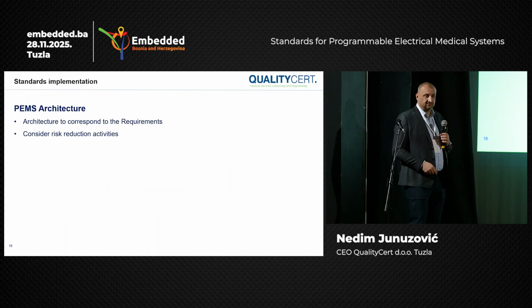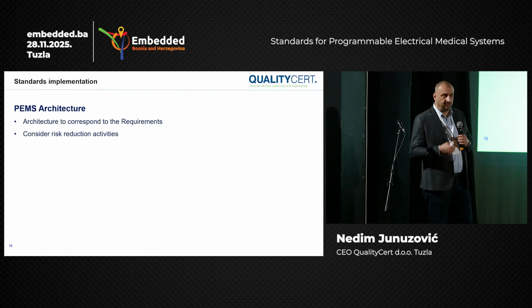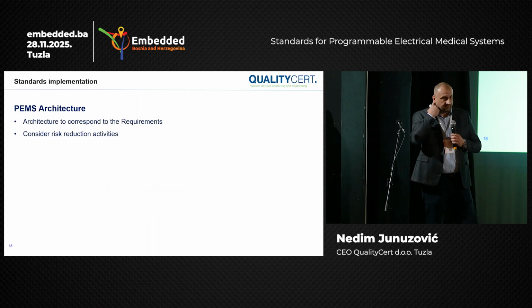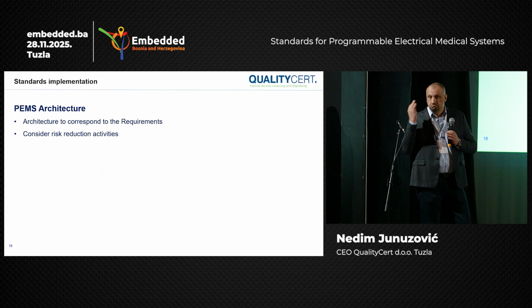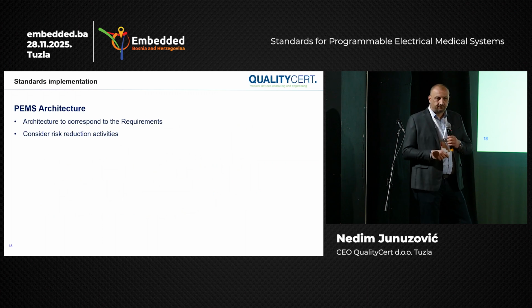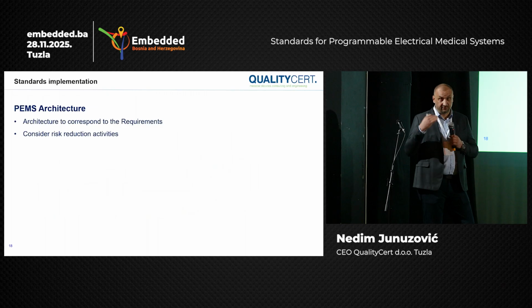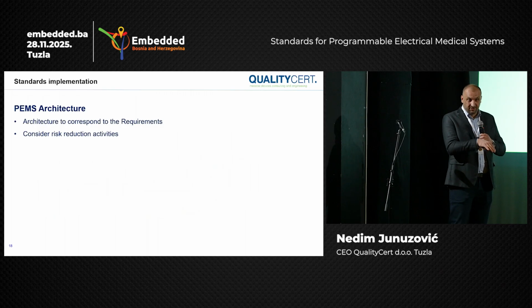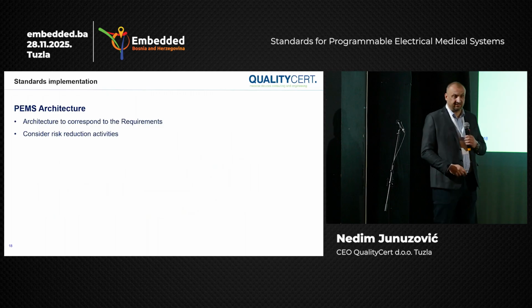Consider risk reduction activities. So when building your architecture for medical electrical equipment, what does it mean? Maybe you will implement some fail-safe functions, or some high integrity characteristic components. You can also consider use of the device and system to make protection in case of foreseeable misuse. That's how the standard calls it - you have to think about what could go wrong with normal use, but a person does misuse the product and so on. So all of those protections would be your design work that you include in the architecture and of course in the design.